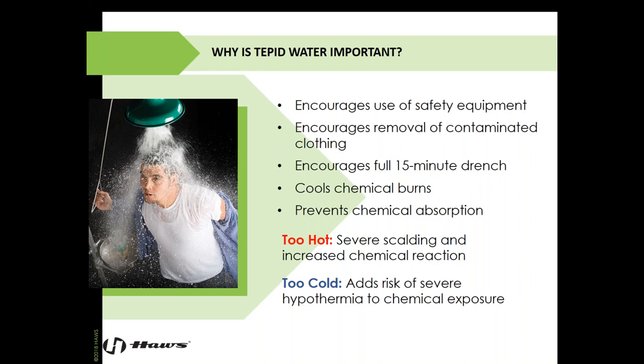Too cold, and we risk the severe hypothermia along with the chemical exposure. So we need to make sure we're providing north of 60 degrees Fahrenheit. I wouldn't be surprised if they increase that in the next version of the standard.